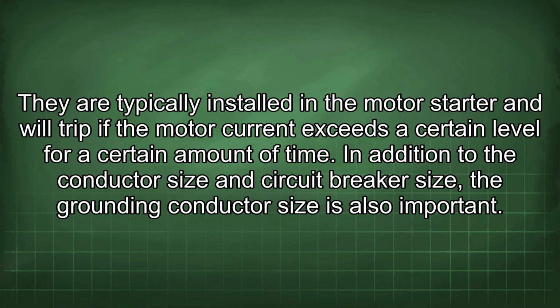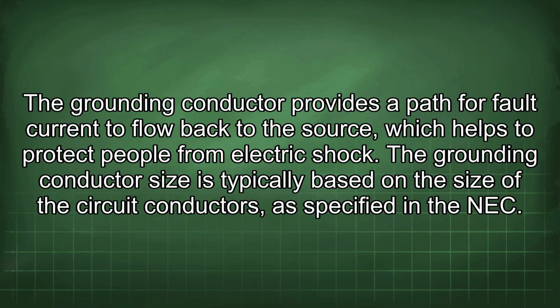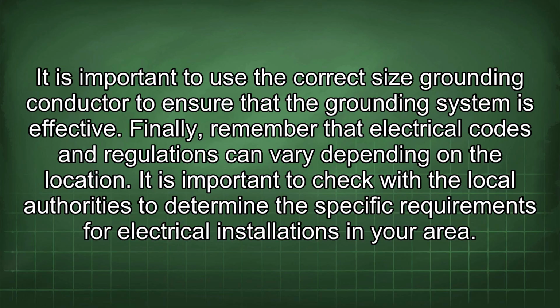In addition to the conductor size and circuit breaker size, the grounding conductor size is also important. The grounding conductor provides a path for fault current to flow back to the source, which helps to protect people from electric shock. The grounding conductor size is typically based on the size of the circuit conductors, as specified in the NEC. It is important to use the correct size grounding conductor to ensure that the grounding system is effective.